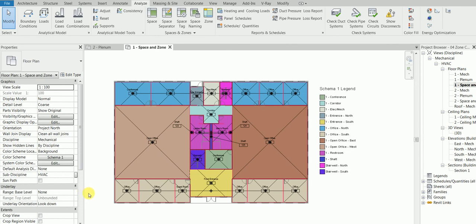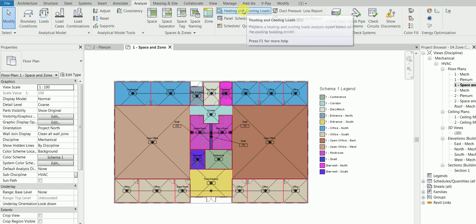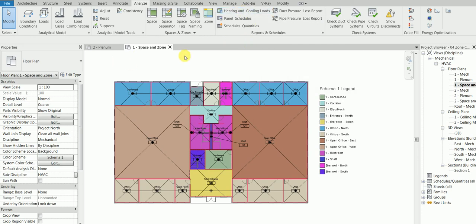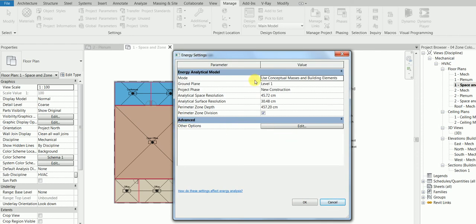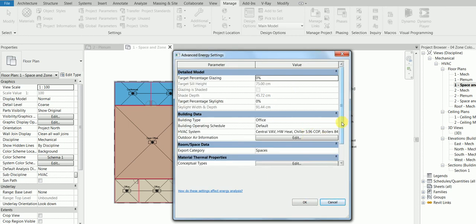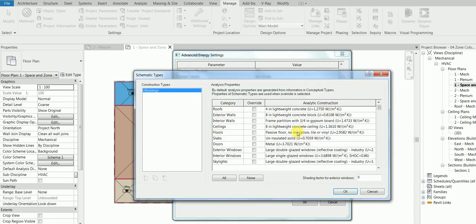In the next part, we will start the load calculation. This is a series of videos — we started from a blank screen, added spaces, and now we'll set up the procedure for heating and cooling loads. Before that, go to the Manage tab, then Project Information, click Energy Settings, then Edit. Make sure the Ground Plane is set to Level 1 — this is the most important setting.